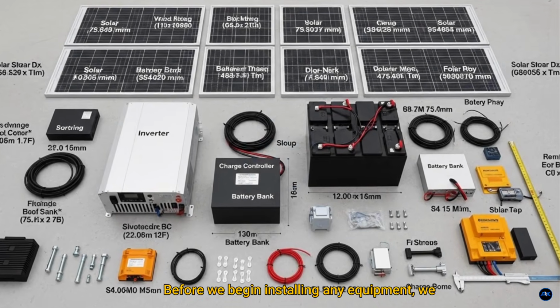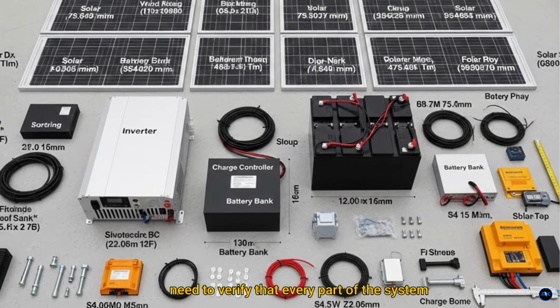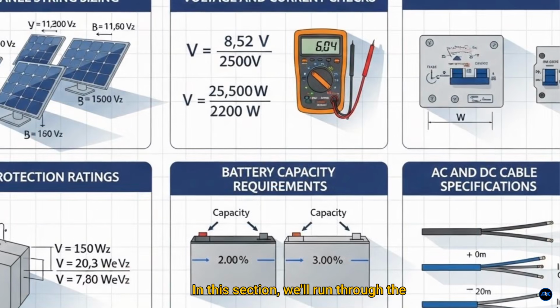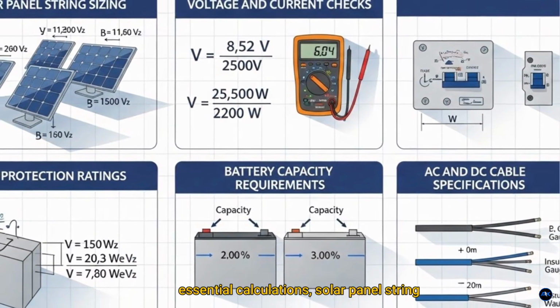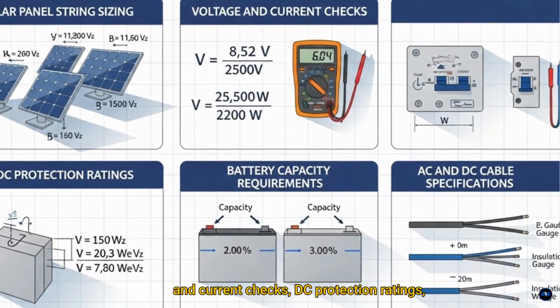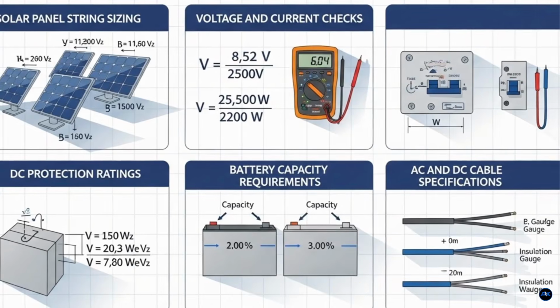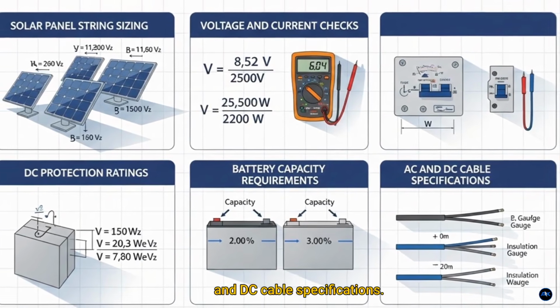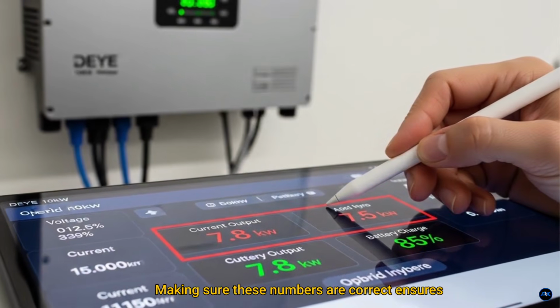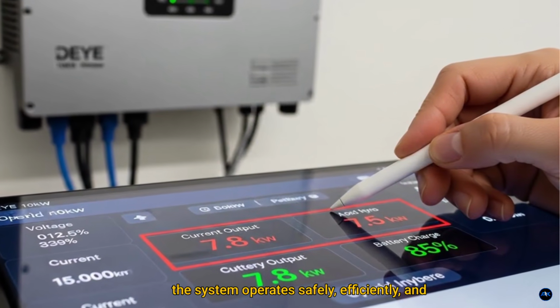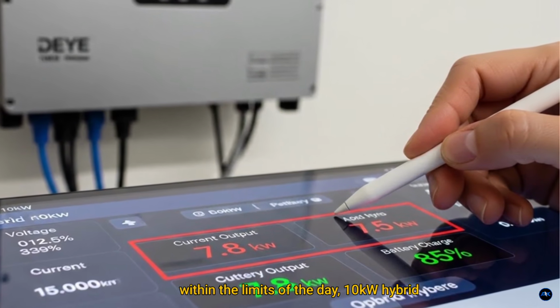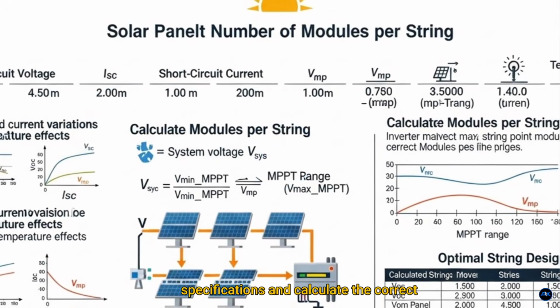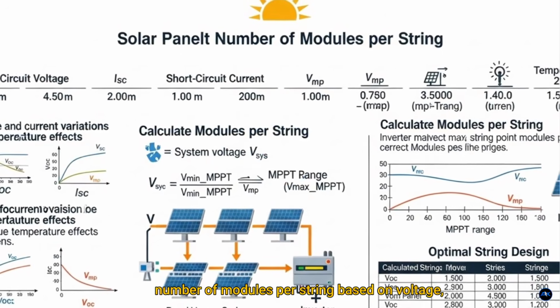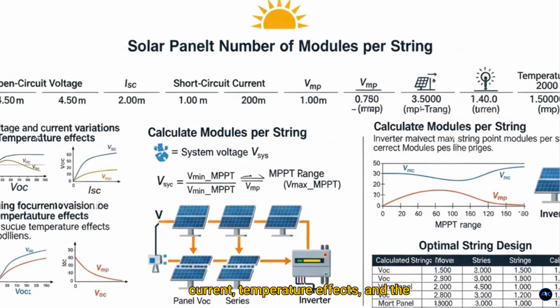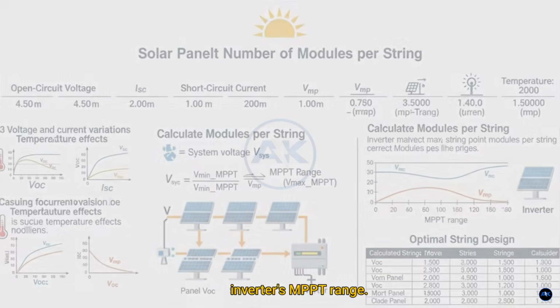Before we begin installing any equipment, we need to verify that every part of the system is correctly sized. In this section, we'll run through the essential calculations: solar panel string sizing, voltage and current checks, DC protection ratings, battery capacity requirements, and all AC and DC cable specifications. Making sure these numbers are correct ensures the system operates safely, efficiently, and within the limits of the DEYE 10kW hybrid inverter. Let's start with the solar panel specifications and calculate the correct number of modules per string based on voltage, current, temperature effects, and the inverter's MPPT range.